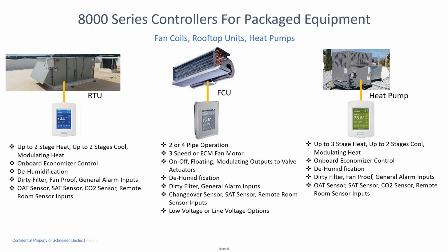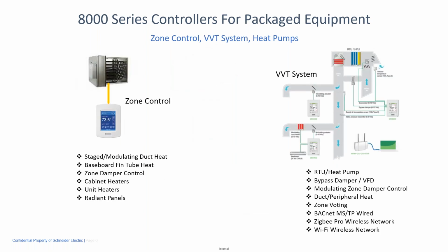The RTU controller and the heat pump controller are basically the same. At the face of the controller, you choose whether it's heat pump or rooftop. If you choose heat pump, you can have up to 3 stages of heat, 2 stages of cool or modulating heat, the economizer, dehumidification, and all the inputs and outputs that are available with the rooftop application. So one controller does rooftop or heat pump, depending upon how you configure the device. These can also be used for zone control, so if you have just a duct heater or maybe baseboard heat, it can do staged heat or modulating heat for zone damper control.